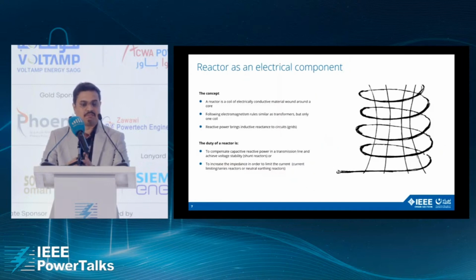Now, what is a reactor? In simple terms, a reactor is a simple coil which is wound around an air core or some gapped core construction, and it has major functions. Normally we have a shunt reactor or a series reactor. Whenever you connect the reactor in shunt, like from line to ground, it absorbs capacitive reactive power. The other function of a reactor, when you connect it in series, is that it increases the system impedance. So you can increase the system impedance to limit the fault current, or when you connect through a neutral grounding reactor, it can limit the unbalance or neutral grounding current through its higher impedance. So these are the two different functions depending upon the position of the reactor in the system, either in series or shunt mode.